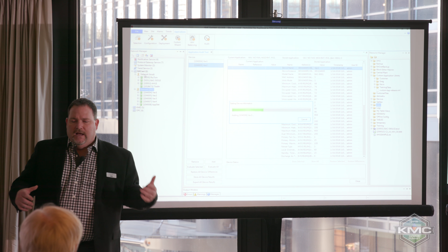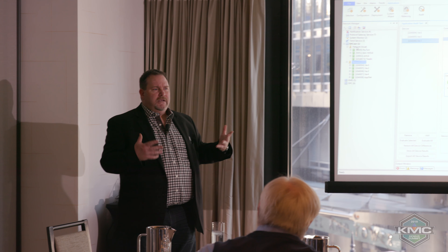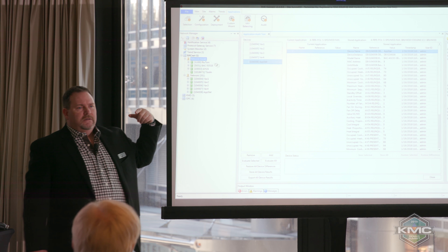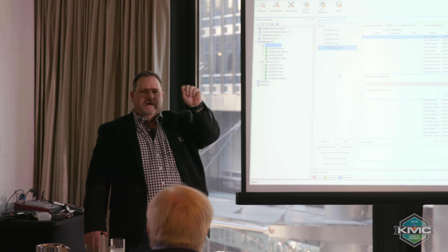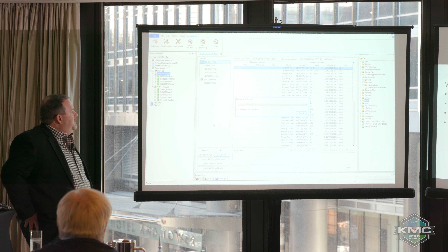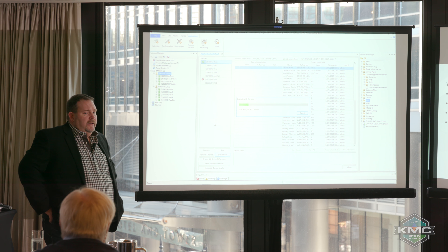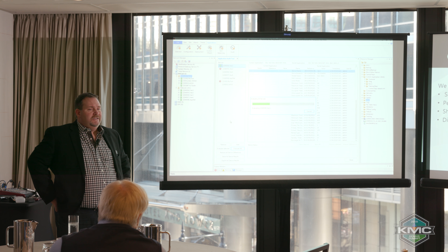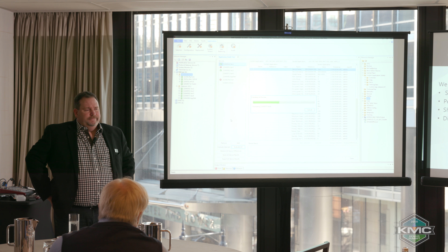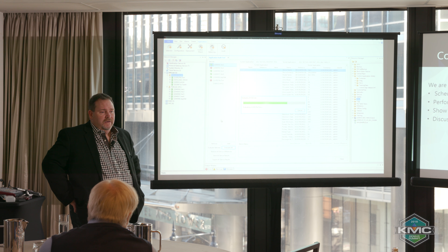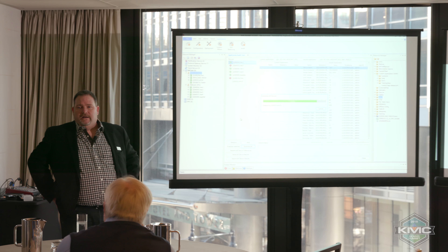What it does is it goes out and says, hey, is this a VAV program? I know what this is - it's in my standard application library. It even goes and says, hey, I know what this air handling program is, it's a custom control. Remember we made the little check marks and said we want to audit these points - that's where that comes into play. So what it's going to do is go out and take a snapshot of all of these controllers. Six months from now when the customer calls and says the setpoints are all weird, the VAVs are acting goofy...